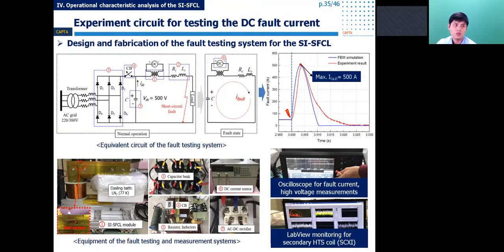Next session is the experimental test and operational characteristics analysis of the lab scale SI-SFCL based on the principle of the voltage source converter based DC power system. A simplified experiment circuit was developed. In principle, in normal operation, this circuit breaker will close, so the normal current of 50 ampere will flow through the SI-SFCL. When the fault occurs, this circuit breaker will open. So the AC side is isolated and the DC side is the capacitor discharge, causing a very high fault current.